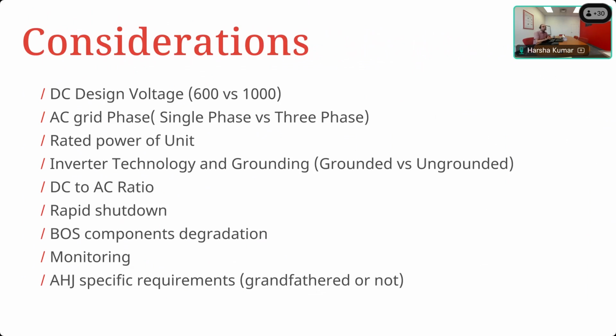The second thing is your AC phase components. You want to make sure that the model of inverter you have in mind is capable of working with whatever phase configuration you choose. Then the next thing is the rated power of the unit. You have to remember that the inverter you're pulling out and the inverter you're putting in might not be of the same AC power capacity.